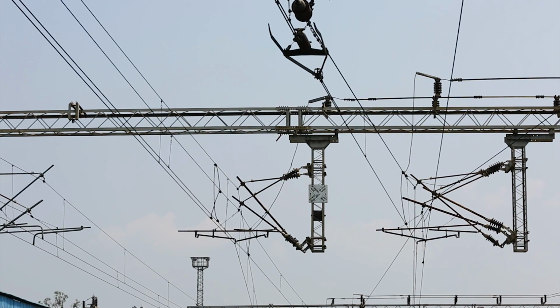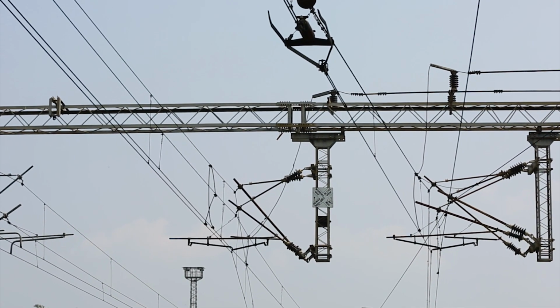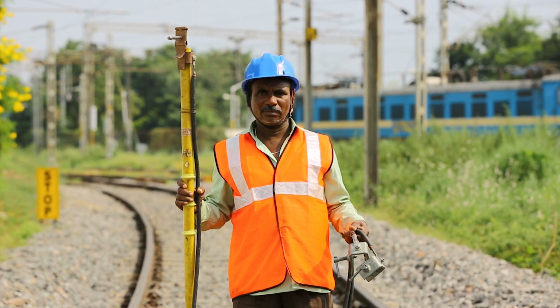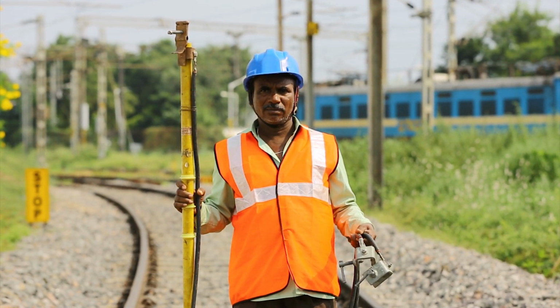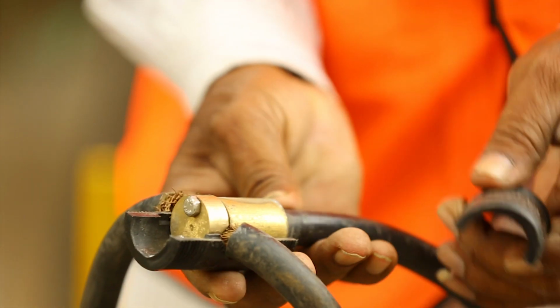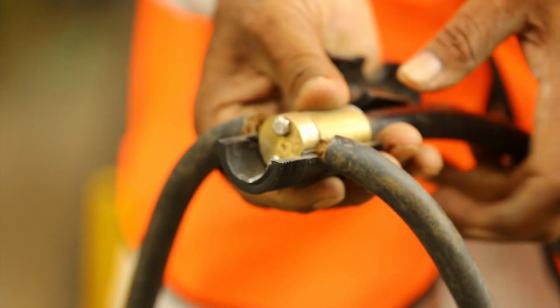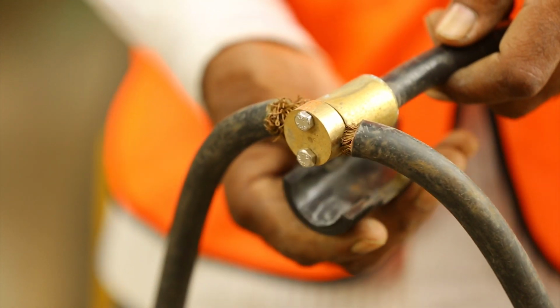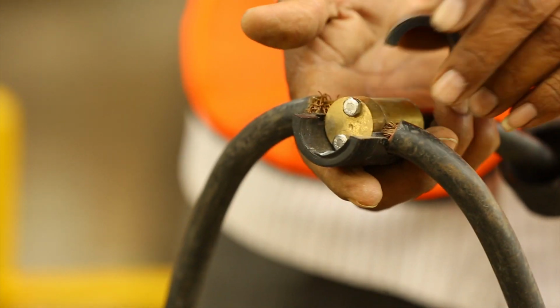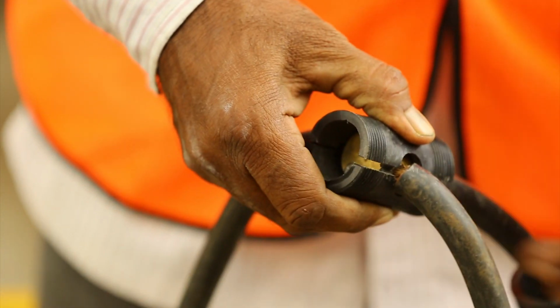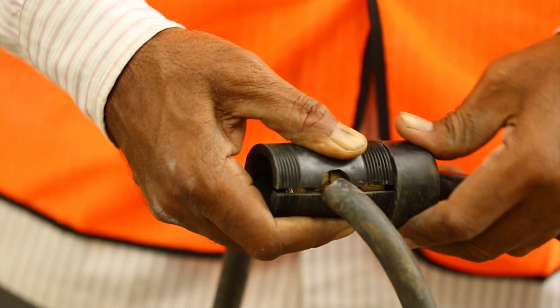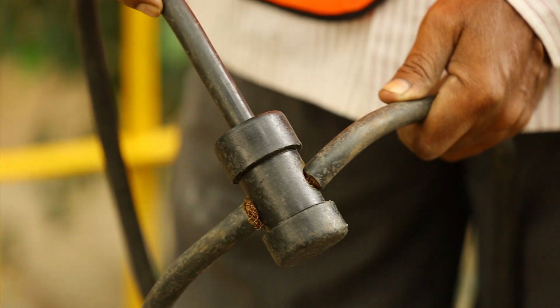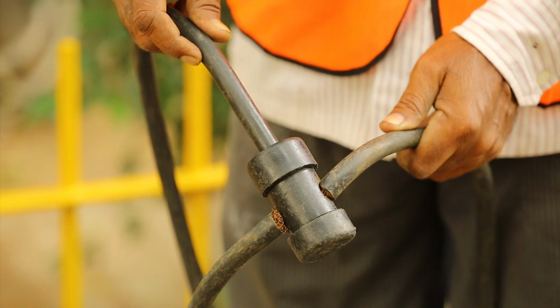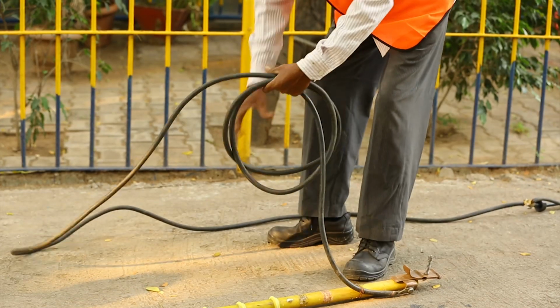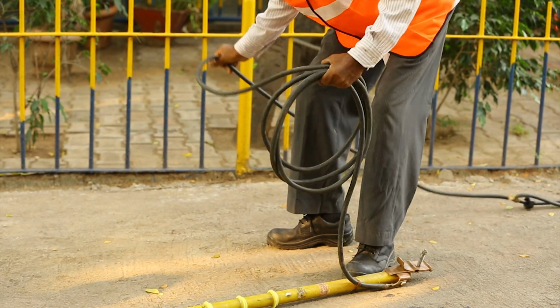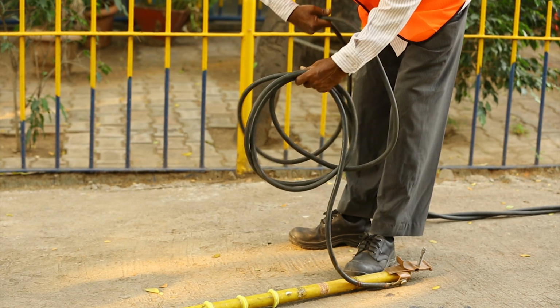No work shall be done above or within a distance of 2 meters from the live OHE. After obtaining the permit to work, a discharge or earthing pole assembly shall be provided on the dead OHE. The cable of the earth pole should be checked for healthiness of strands and renewed if more than 20% of strands are broken. The cable of the earth pole shall be flexible and should have adequate cross-section to withstand short-circuit currents.